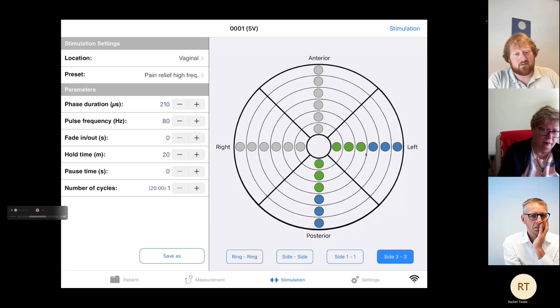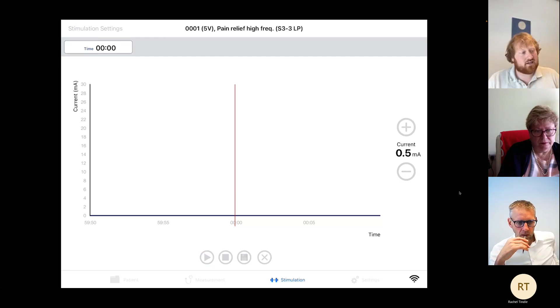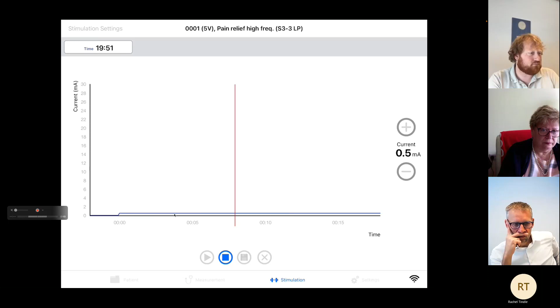Now, if we select the settings we would like to use, you go to the top left corner to go to the stimulation to actually perform it. And then you have a very simple representation, just a line graph, a red line to show you where you are exactly. And on the right side you have a plus and a minus to increase or decrease the current you're giving the patient. Now, if I press the start button, again, it takes a second because the system does a number of safety checks, and then you actually start the stimulation. Now, in an active period, which is represented by the blue line below, I can increase the current.